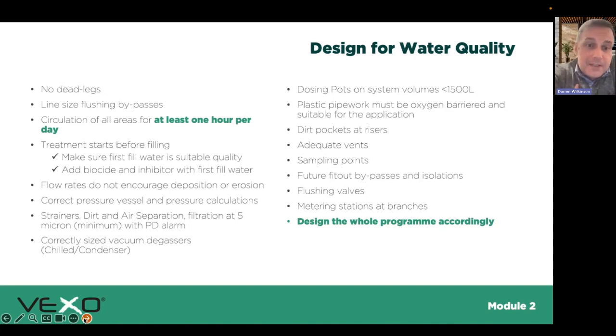Strainers and dirt and air separators, typically filtration at 5 micron and with a form of an alarm. So, whether it's one or all of those technologies, you need that sort of technology. Strainers catch your bricks, to use a phrase. They will catch the big heavy stuff in the first pass, so you need your strainers. Dirt and air separators catch the little granular stuff that will drop out very quickly. And then finally you're left with this very fine sand, which is where you need your filtration as well.